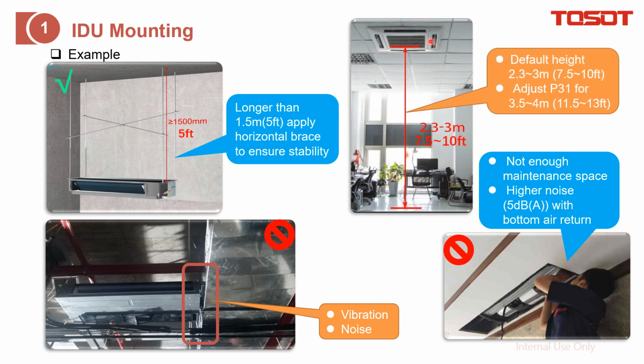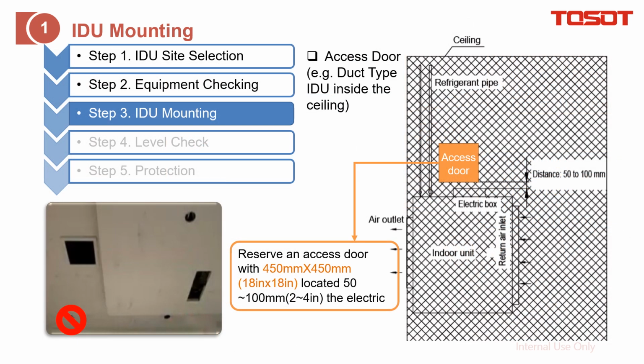For the cassette type, the default setting will support up to 10 feet from the grill to the floor, and for more than this value, please adjust P31 to increase the fan RPM to raise the ESP. And not only the clearance, but also the access door you need to consider for the indoor unit, especially when you're going to do the maintenance. And here is the reference size of the access door.